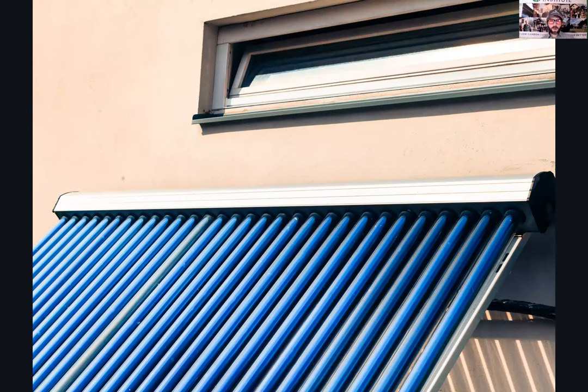So, you know, one of you brought this up earlier, and it wasn't correct, but that's okay. But solar water heating is, and you tell me what you're seeing out there, it just seems to be a technology that is pretty much on its way out. And all of the renewable energy installers that I know, who used to install this, have just abandoned it. Part of the reason is durability, cost for maintenance and upkeep, and potential leaks.